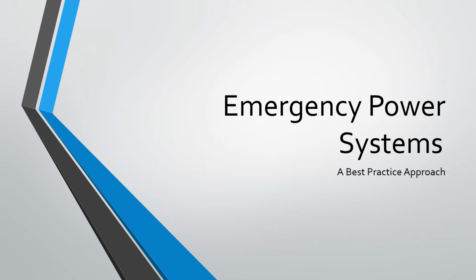But one other thing to distinguish is that not all transfer switches have to come over within 10 seconds. You may have an emergency system that has a transfer switch that is tied to, let's say, a business office. It's a business function, pure business, not patient, not clinical at all. It may be an extension or a building with its own transfer switch, with its own panels and everything else.